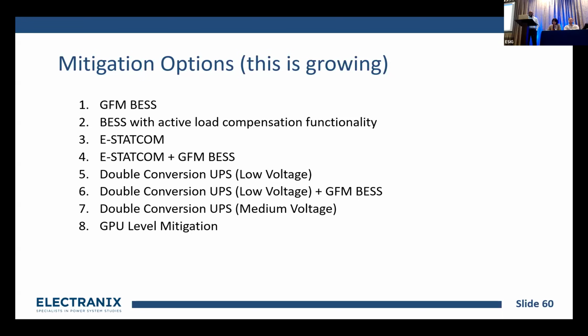And then we have a second type, a BESS with active controller compensation, where you actively measure the power fluctuations and inject the reverse, or opposite polarity, to make it flatten out. I don't have a name for that, so I put BESS with active power load compensation functionality. And the third one is the eStatCom. That is another device that actively compensates load using supercapacitors. And a fourth one is a combined solution, an eStatCom together with a GFM BESS, which is typically required for an eStatCom, because the eStatCom supercapacitor energy storage is in seconds levels, not in minutes levels. So if you have a low frequency load oscillation, you probably need additional compensation on top of the eStatCom, which is why I put number 4 as the eStatCom plus the GFM BESS.